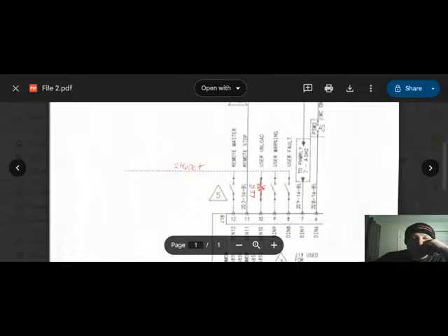The reason being, if the lights are on, this relay coil is going to be excited and it is going to change states and these contacts will open. When that happens, that manual unload signal goes away and the compressor will run as normal. When the lights go off and the relay coil is de-energized, these contacts will close and this user unload signal can come in here and unload the air compressor.